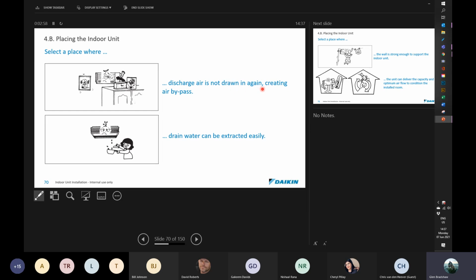Discharge air must not be drawn in again, creating an air bypass. So basically, we don't want the air to short circuit from the unit. So don't place the unit in areas where the air is going to bounce back directly into its return air. It's also going to cause the unit to short circuit or short cycle.